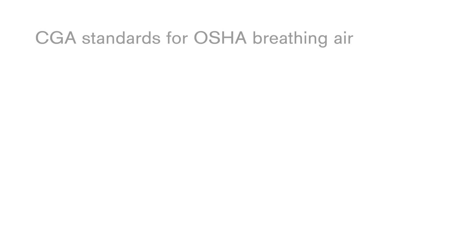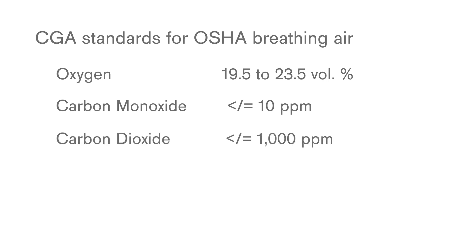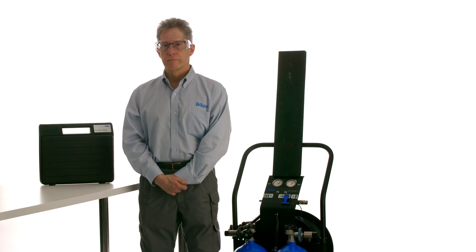The CGA standard specifies oxygen to be 19.5 to 23.5 volume percent, carbon monoxide less than or equal to 10 ppm, carbon dioxide less than or equal to 1000 ppm, condensed oil less than or equal to 5 mg per cubic meter, and water content less than or equal to 54 mg per cubic meter for OSHA breathing air. Other standards vary slightly.